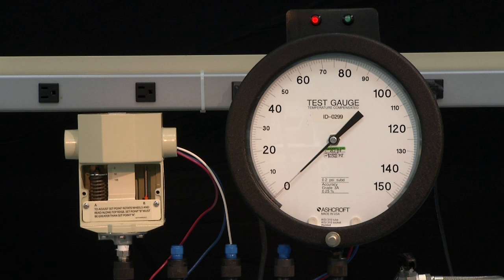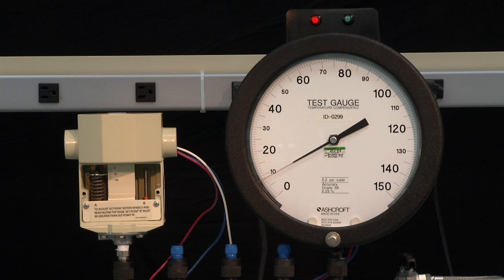The first step of calibration is to exercise the switch to make sure it is operating correctly. To exercise a switch, start from zero PSI and increase to full range of the switch, in this case 100 PSI, and then return back to zero.